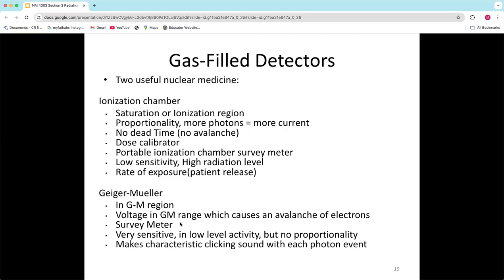Now, like I said, what I want you to do is go and look at what you have at your work. As manufacturers have made these things over time, they've combined them, and you can almost do both with one. There are a lot of meters where, depending on the setting, it ups the voltage and now you're using it as a Geiger-Müller. If you lower the voltage, now you're getting a measurement and using it as an ionization chamber.